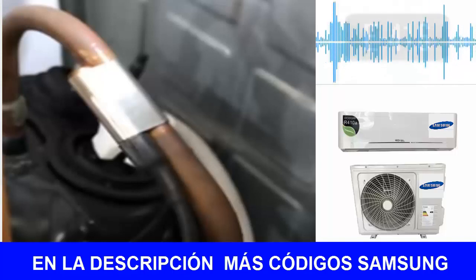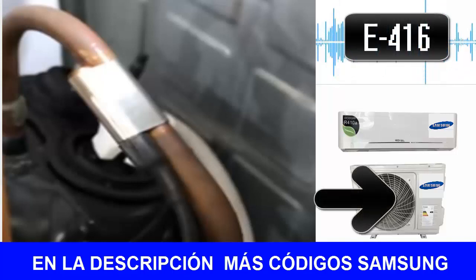11. Fault represented by error code E416. This code warns that the discharge temperature has exceeded permissible limits. A. Verify air circulation and ensure the system is functioning correctly. For additional codes, refer to the video description.